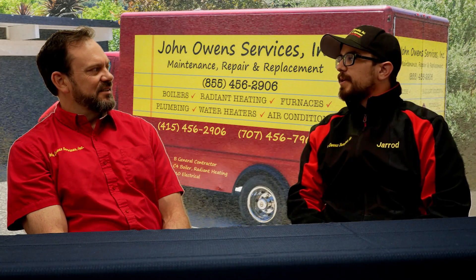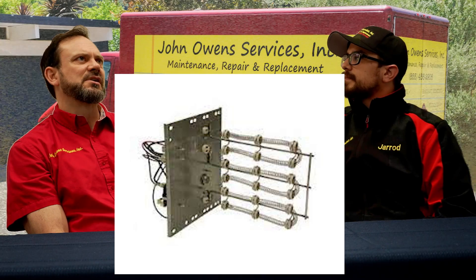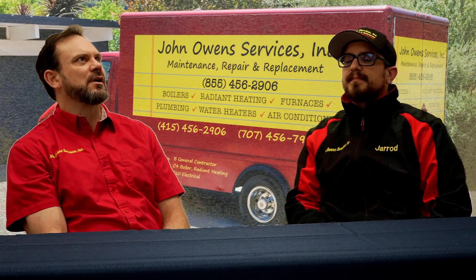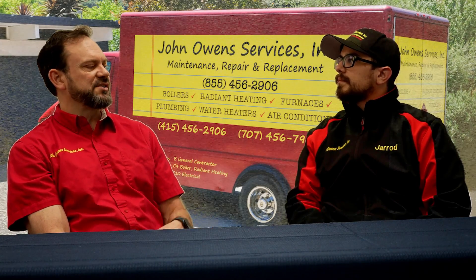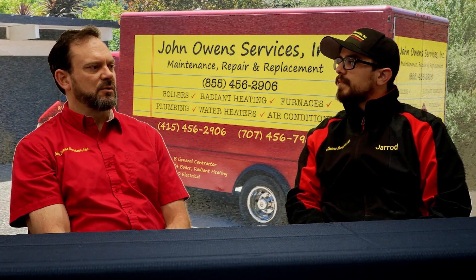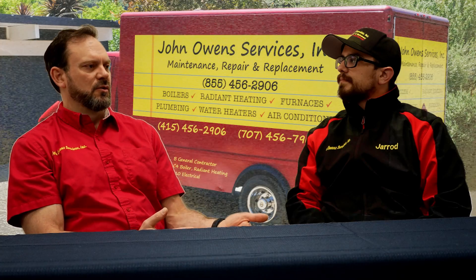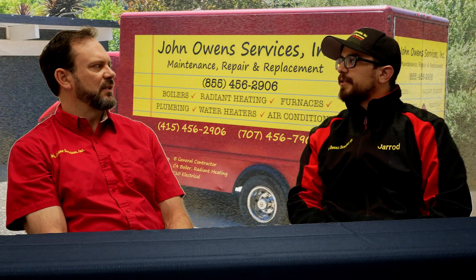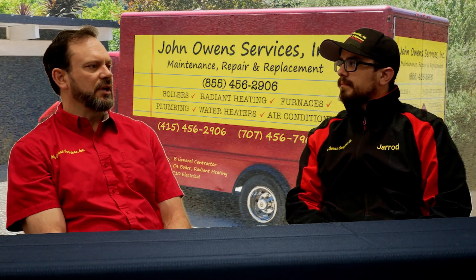The second backup option is an electric heat strip. I compare it to a toaster element — basically that, but using a lot of power. It takes care of the house while the system is in defrost mode, and you can get larger ones that will actually heat the house. But they draw a lot of power. Part of the goal here is to be as energy efficient as possible — there's no point in decarbonizing if you're burning a bunch of electricity in a heat strip, especially if you have solar. It will work, but it requires a separate circuit, drives up installation cost, and has real efficiency downsides.